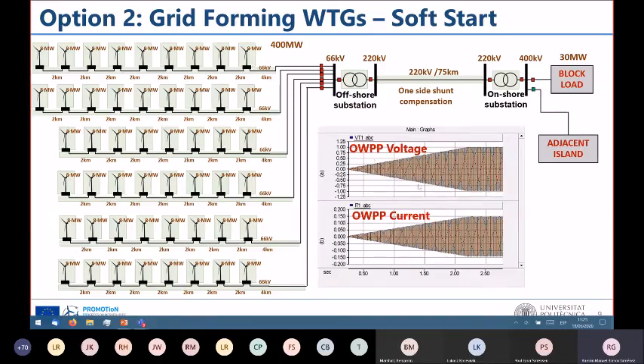There are some questions about different ramp rates, but what we found, and what is generally found, is that overvoltages and inrush currents and resonances are much more largely mitigated in this kind of process. Obviously, the issues with block load and the issues with faults are exactly the same once the system is operating. So this is for HVAC connected.